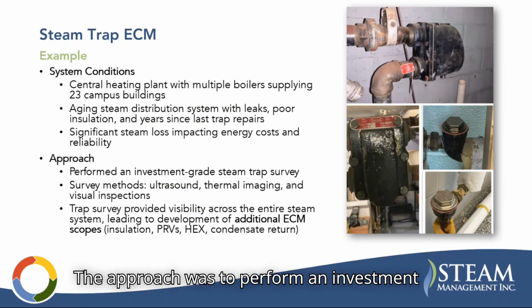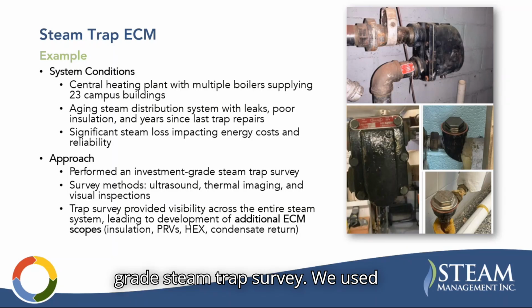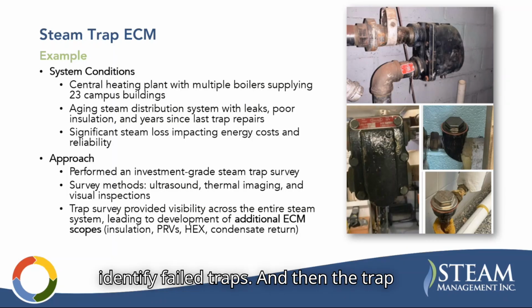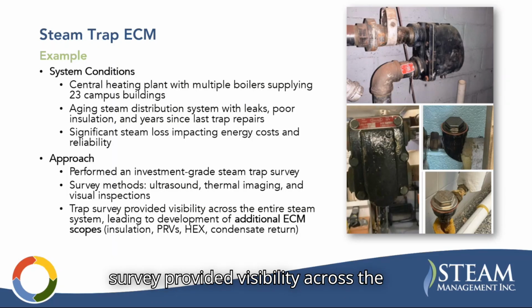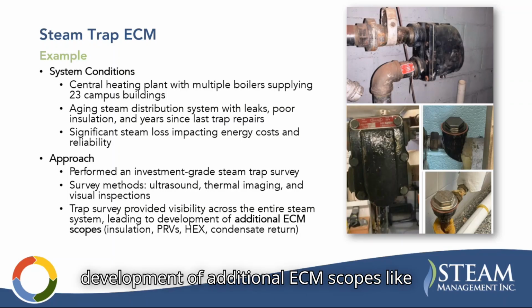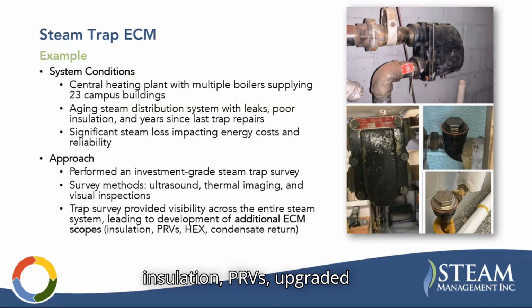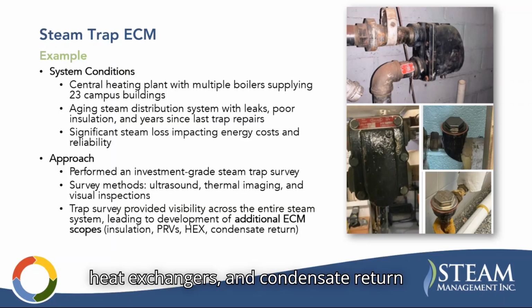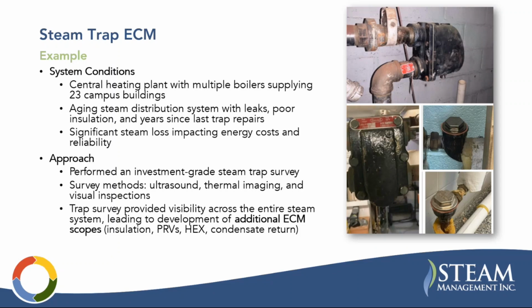The approach was to perform an investment grade steam trap survey. We used ultrasonic testing, thermal imaging, and visual inspections to identify failed traps. And then the trap survey provided visibility across the entire steam system, leading to the development of additional ECM scopes like insulation, PRVs, upgraded heat exchangers, and condensate return improvements.